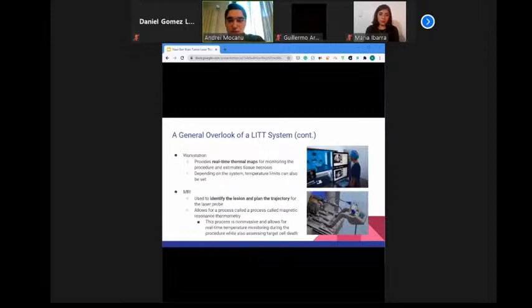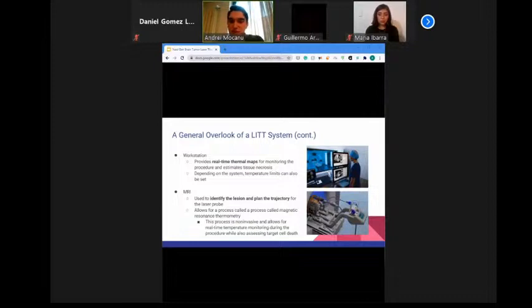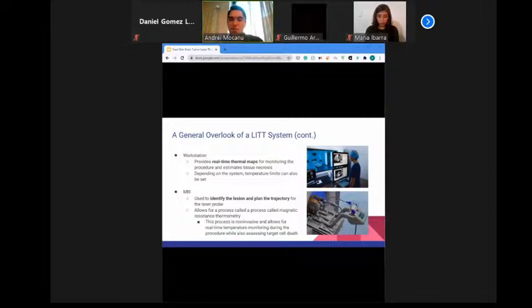MRI images obtained before and during the LITT procedure are sent to a linked workstation, which provides real-time thermal maps for monitoring the procedure and estimates tissue necrosis. With the Visualase system, one can assign temperature limits as safety points to trigger system deactivation, preventing undesired thermal damage to nearby structures. The Neuroblate system has a thermocouple at the tip of the probe that determines baseline brain temperature and regulates the amount of CO2 circulating through the tip to maintain a predetermined temperature range.